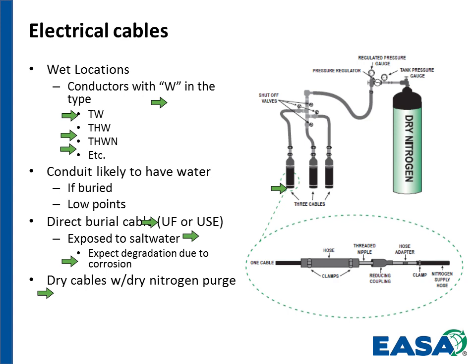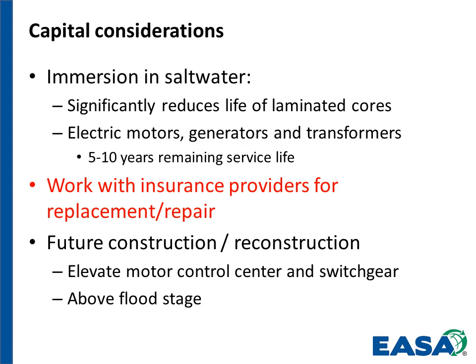The money, capital considerations. Any electric motor or generator that's been immersed in salt water, if it's been allowed to dry or if it's not very, very thoroughly cleaned, you can expect the laminated core life to start deteriorating. In an emergency like this, certainly getting them cleaned and back in service gets you back in production, but you need to recognize that you need to budget and plan for replacement of many, if not most, of those electric motors and generators within the next 5 to 10 years.